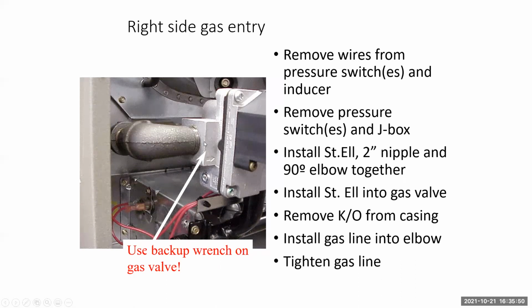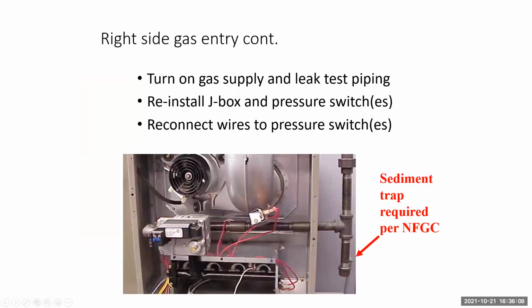And when you're tightening in here, use a backup wrench on that gas valve. They didn't just put a pretty square there to redesign things for their own good. They put it there for the purpose of you guys using it to have something to grab onto so you're not snapping gas valves. So use a backup on that when you're tightening in that 90. Showing once you're in, then you can get your J box and your pressure switches back in.